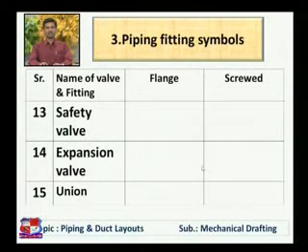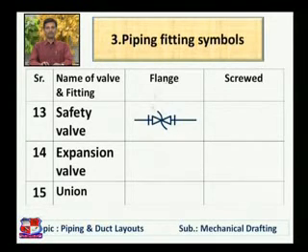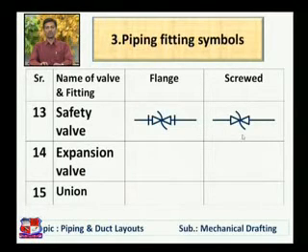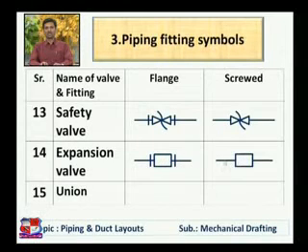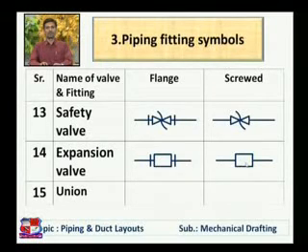Safety valve is used in the pipeline for pipeline safety. Its symbol is drawn with two lines for a flanged connection and without lines for a screwed connection. The expansion valve is shown by a rectangle — with two flanges for a flanged connection, or just a plain rectangle for a screwed connection. This symbol indicates that fluid expands inside the valve, pressure reduces, and expansion occurs.